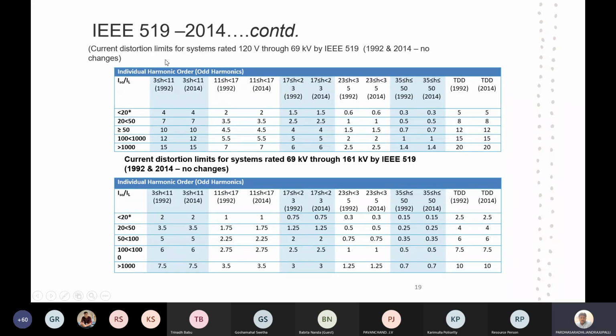This is the current distortion limit for systems rated 120 volts through 69 kV. ISC by IL is the short circuit ratio, the ratio of short circuit current to the maximum fundamental load current. This is the harmonics accepted, that is TDD, which refers to total demand distortion. We all know THD refers to one cycle or two cycles or a couple of cycles, whereas TDD, if you want to check it for more cycles over a particular time period, will be called total demand distortion.